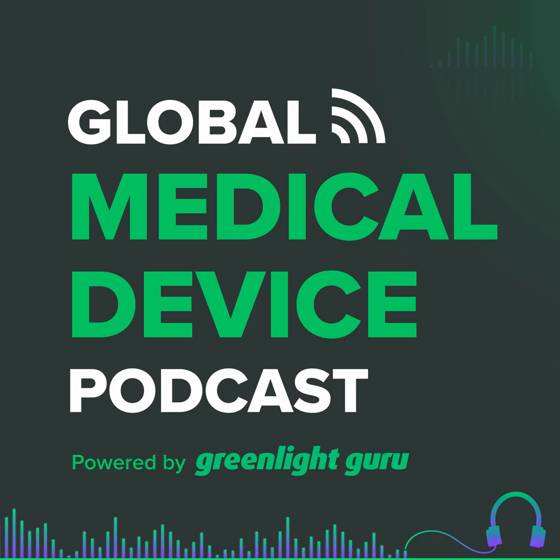And one other thing that I'll mention, and then if you want to chime in further, Etienne, by all means, please feel free. Not only does it apply to any medical device, it also applies to certain combination products, specifically device-led combination products. That is a combination product where the primary mode of action, or PMOA, is device. Like, for example, a drug-eluting stent. It would not apply to other combination products because I don't think there's a snowball's chance here in Southern California that CDER or CBER, the drug or the biologic side of FDA, will ever in a million years buy into this concept of a predetermined change control plan, but CDRH has.